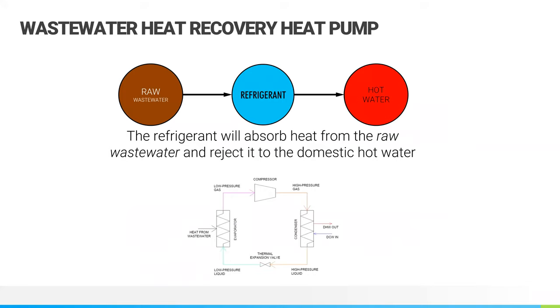So circling back to wastewater heat recovery. What we'd see on a wastewater heat recovery heat pump is raw wastewater transferring to a refrigerant loop, transferring to a hot water loop. The refrigerant absorbs heat from the raw wastewater, and then that heat gets rejected to another coil that creates your domestic hot water for your building. That's how we're able to close that endless loop of just dumping energy down the drain on a building by building basis, and capture that energy from the wastewater and transfer it into an all electric and super highly efficient domestic hot water source.